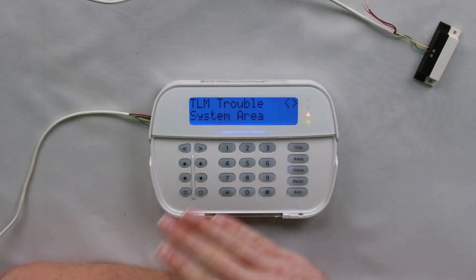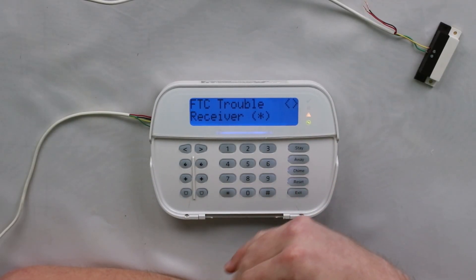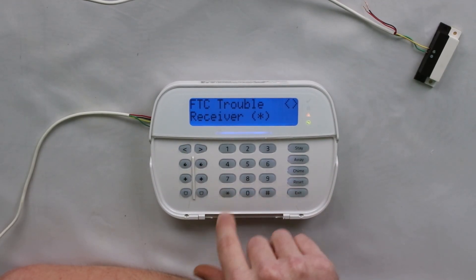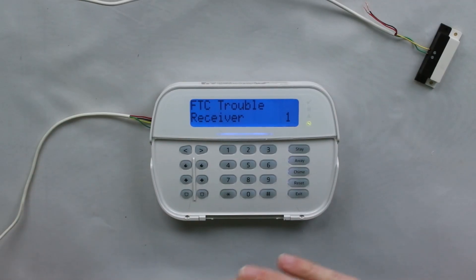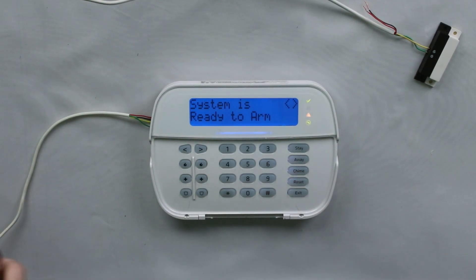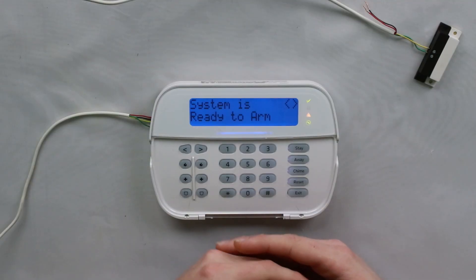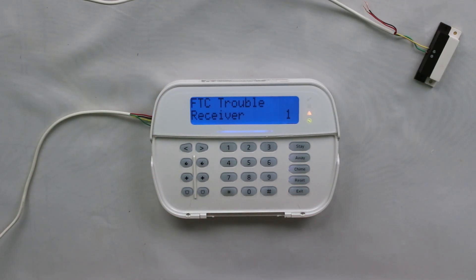And then if you hit star, it's going to say TLM, that's because I had to turn the phone line on. But you'll also see, this is what you would normally see with any communicator, is FTC trouble receiver. And then it's going to have a star there. If you hit star, it is going to tell you what receiver had the failure to communicate. So this is where it can get a little confusing because the system has multiple receivers. And whenever you set the system up to communicate using a different communication path, either the communicator determines what receivers it's going to use or whoever set up your panel is going to do so. As you can see on my trouble there, I had a failure to communicate receiver one. So that means that because I set up receiver one's phone number, that's where it tried to send the signal out.